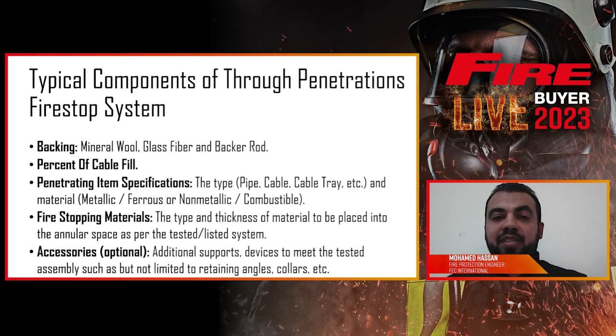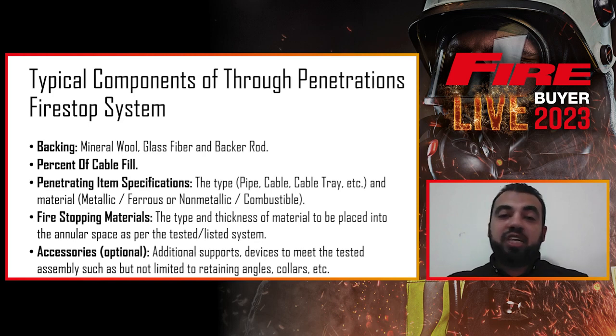Normally, the cable filling percentage is around 40%, and in rare cases goes to 65%. So if you have a hole or opening that is full of cables, and the percentage of filling seems very high, I believe this will not be a standard system, and you might need to go to engineering judgment or change the size of the opening.